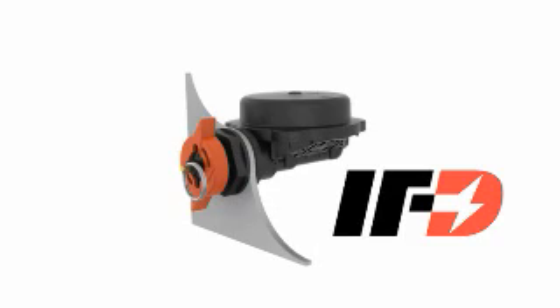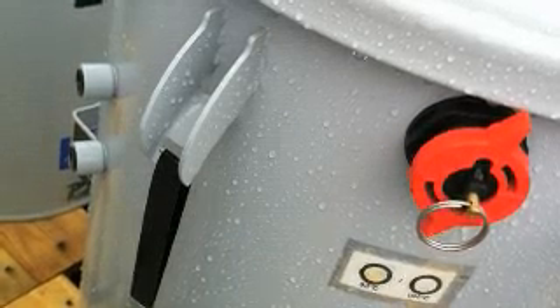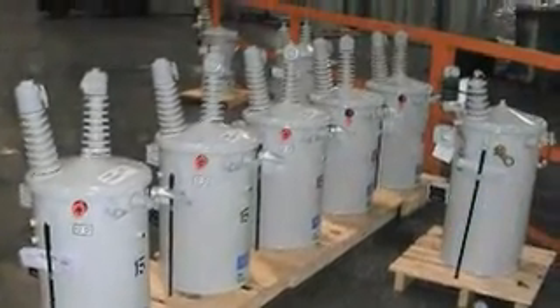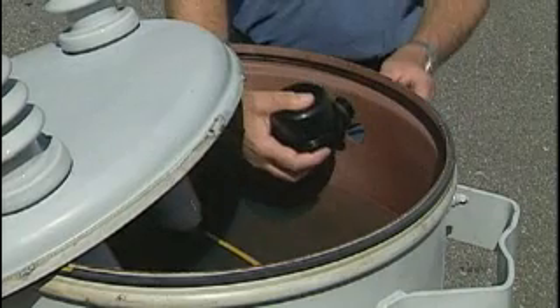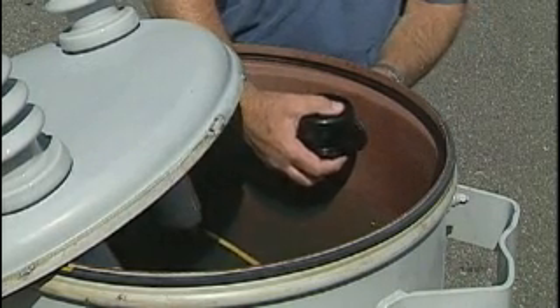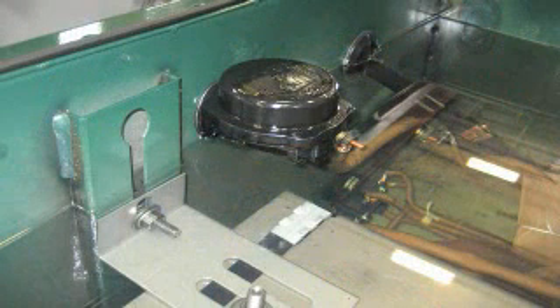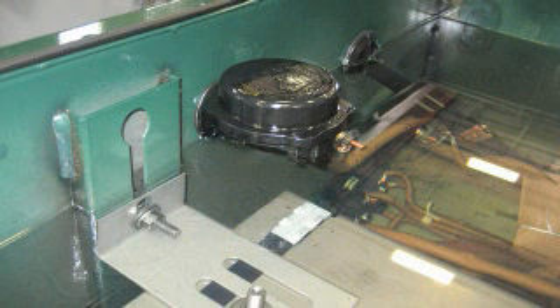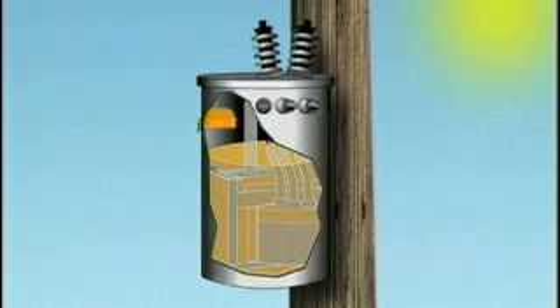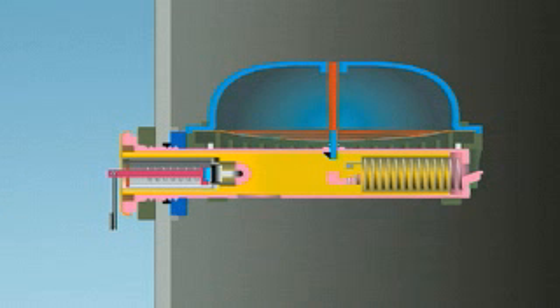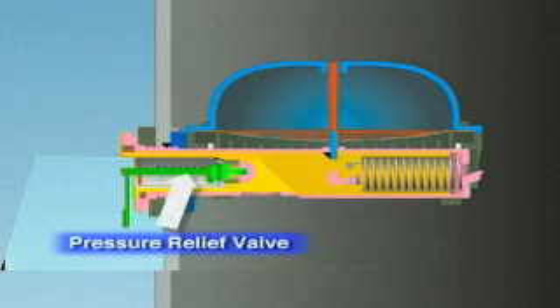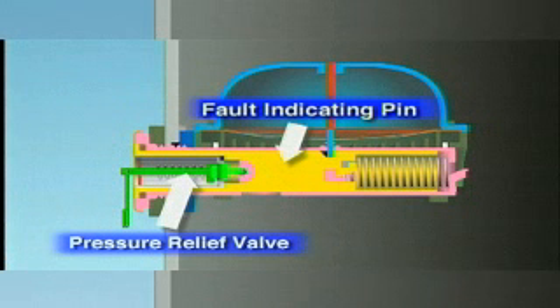The IFD sensor is a mechanical device requiring no electrical connections. IFDs are inexpensive to purchase and are easy to install in new transformers during manufacturing. They can also be retrofitted in existing transformers. When installed on the side of a transformer above the oil level, the IFD does not interfere with any of the electrical components inside the transformer. The IFD serves a dual purpose, as a pressure relief valve, or PRV, and as a fault detector.